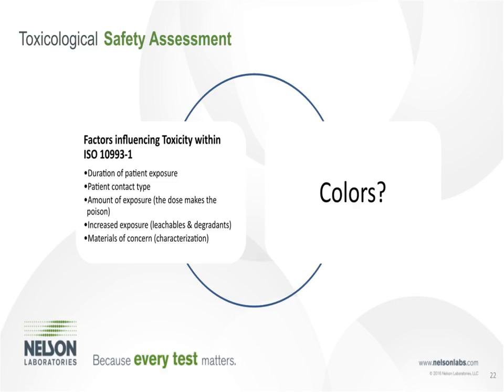A lot of times, we at Nelson Labs have to be the generator of that information. We contact the color supplier, get an NDA in place, and get that information independently of you, because I guess they figure we can't reproduce that colorant like you can. So if you have a colorant in your device, pay particular attention, especially if that colorant is prolonged or long-term contact, or if you see particulates or color changes in your extract media with your biocompatibility. Those are things the FDA is looking for.